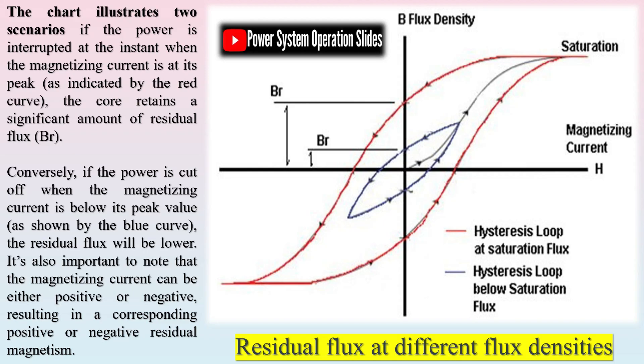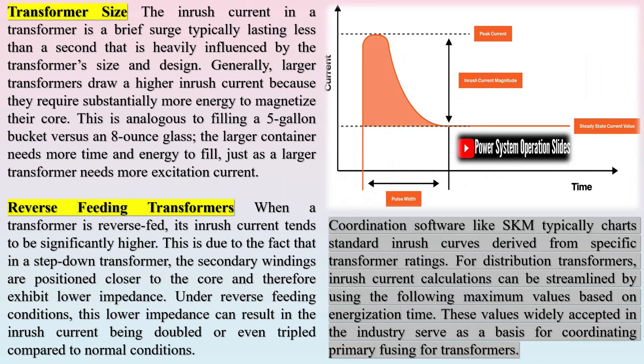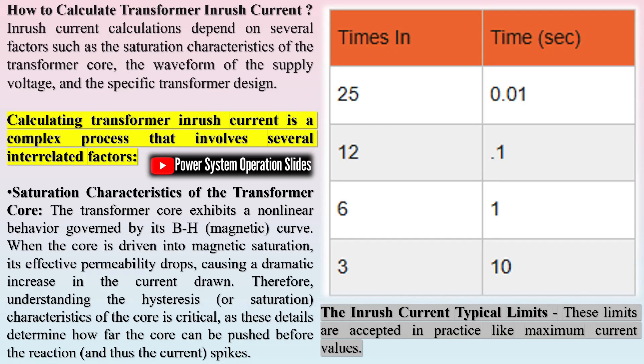The amount of inrush current depends on the excitation current needed to establish proper mutual induction between the primary and secondary coils. Moreover, how efficiently the core is constructed also matters. A well-built core requires less inrush effort compared to one that is poorly assembled or damaged — think of it like trying to push a car with a dead battery, where significant extra effort is required just to set it in motion. Once the core is fully energized, a smaller excitation current continues to maintain the magnetic field, with any excess being seen as no-load losses.